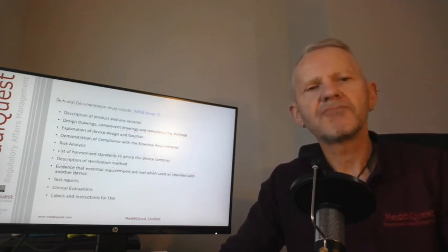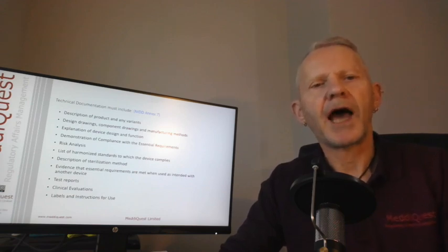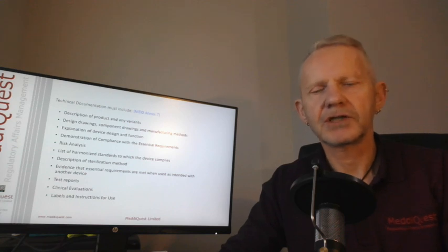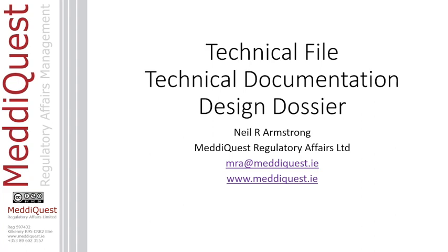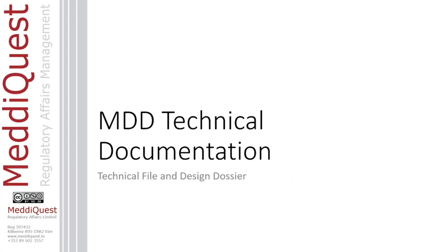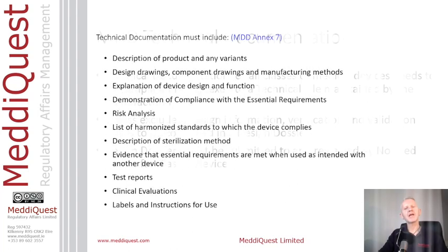Now, what was actually required in this technical documentation was laid down in Annex 7 of the Medical Device Directive. There is nothing unusual or unconventional in this technical documentation.